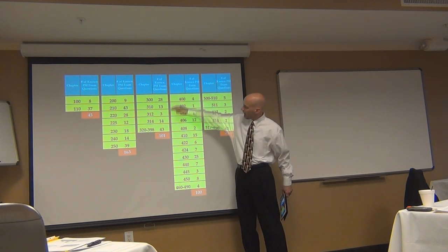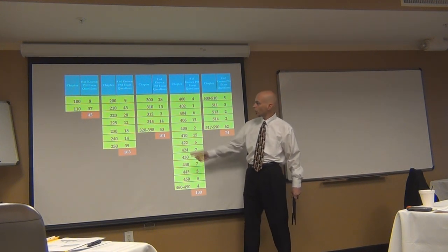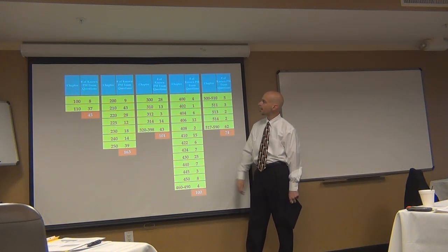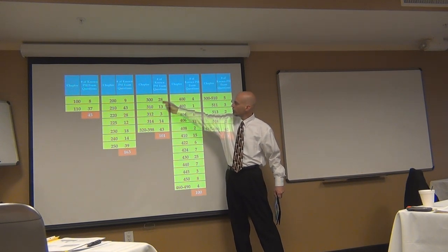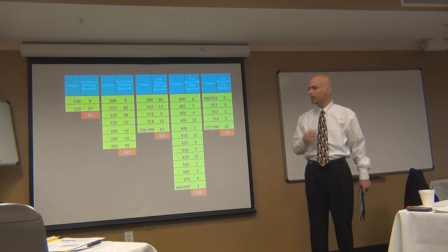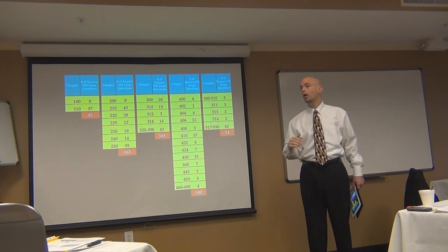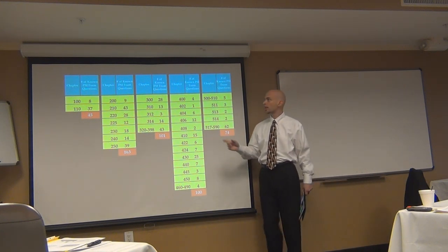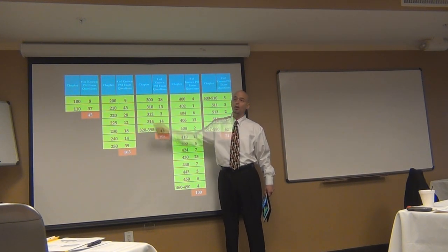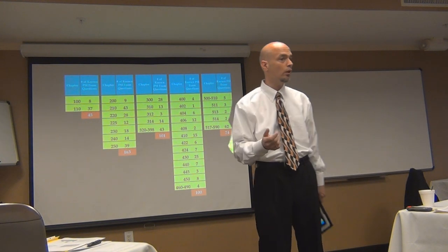Out of Chapter 3, you look at that breakdown — this is all the back part of Chapter 3, which is all your wiring types and raceways. We have 43 throughout the back of that, probably closer to about 50. The other real big one, almost as big as 220, is Article 300. Even though there are 28 listed there, that's even kind of a misleading number because Article 300 is the underlying bedrock of electrical installation principles. You may have a component out of 300 that will make your other article go one way or the other.